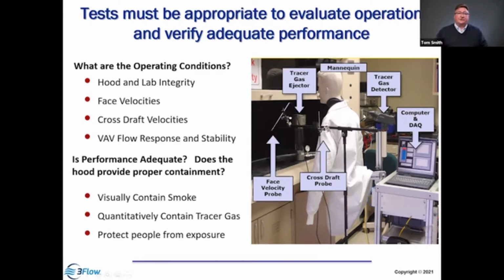In that case, we're going to use a mannequin to simulate a person. We're generating a tracer gas inside the hood, pulling breathing zone samples and measuring them with the detector to see if anything escapes out of the hood. And so if the hood is functioning properly, and we're not seeing anything escaping out of the hood during this test, we have a high probability that it's going to work to protect the occupants.